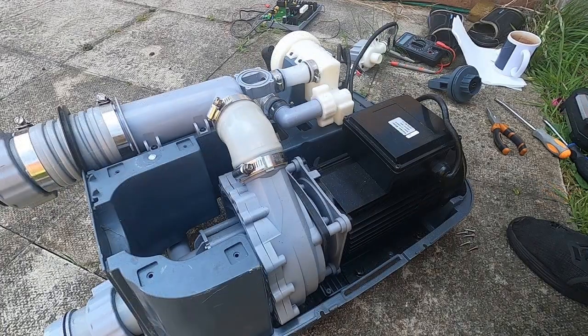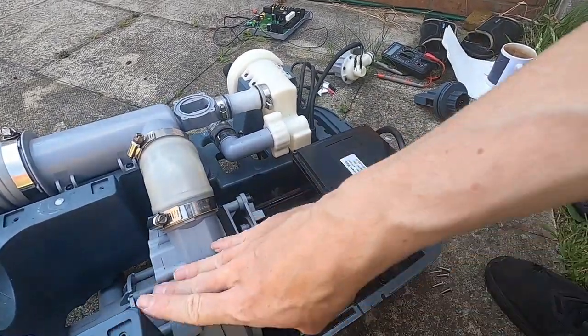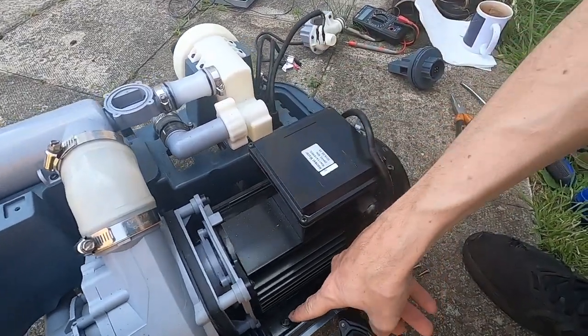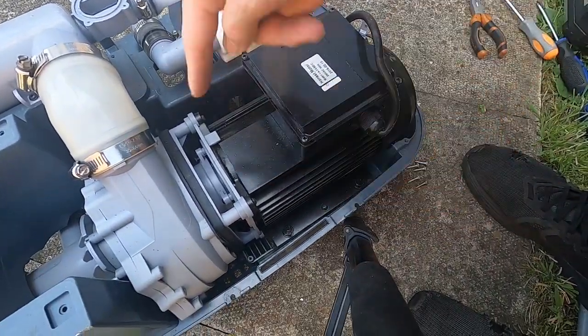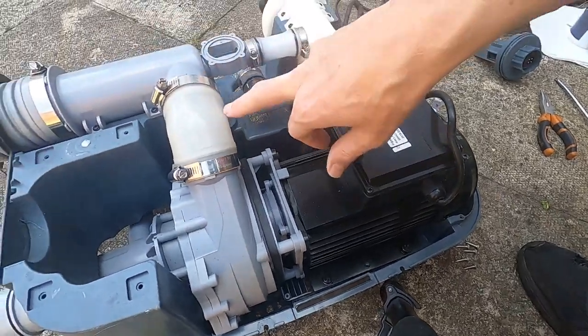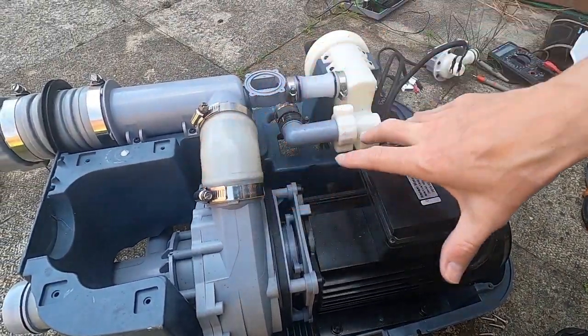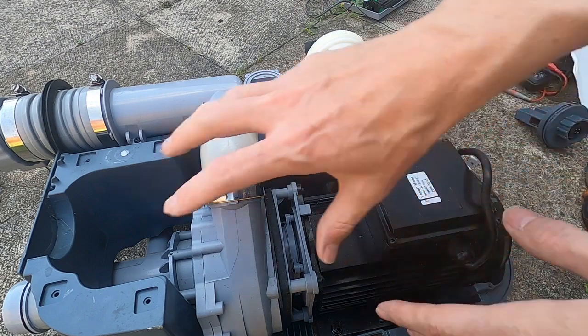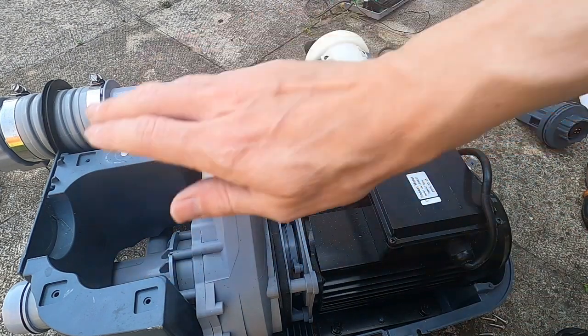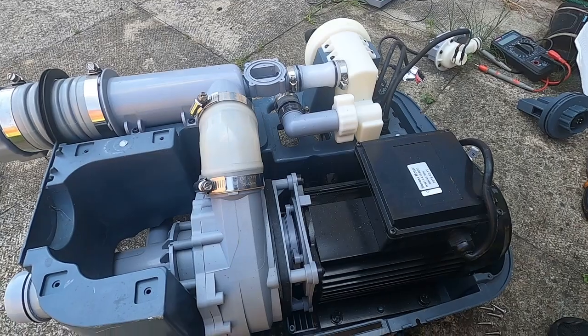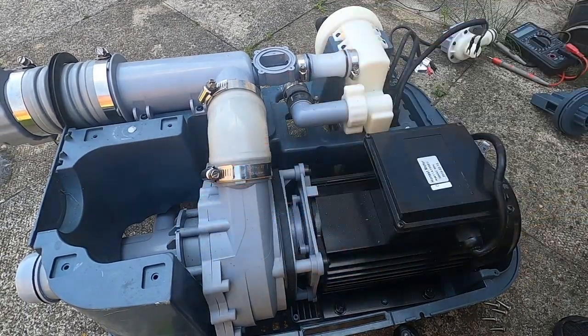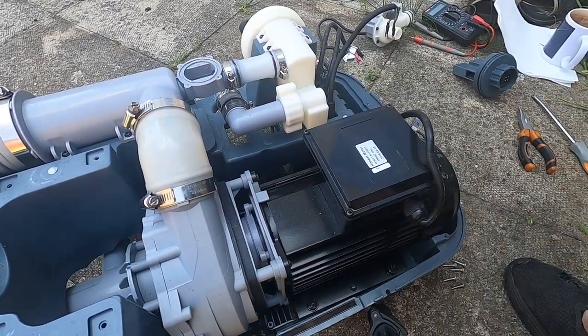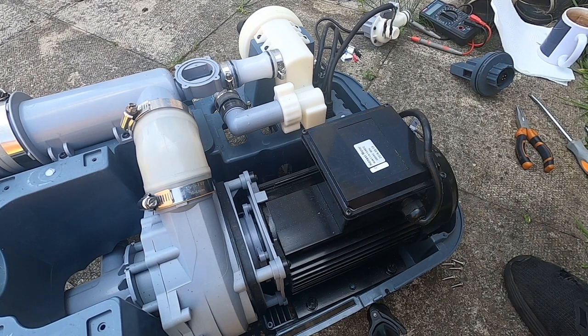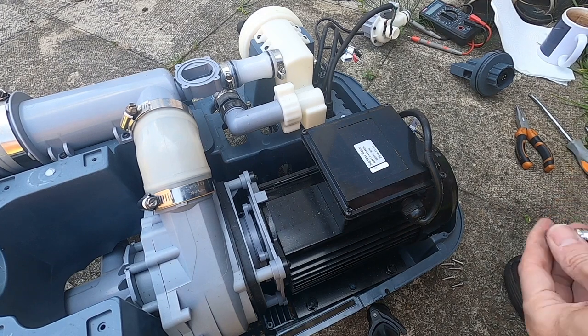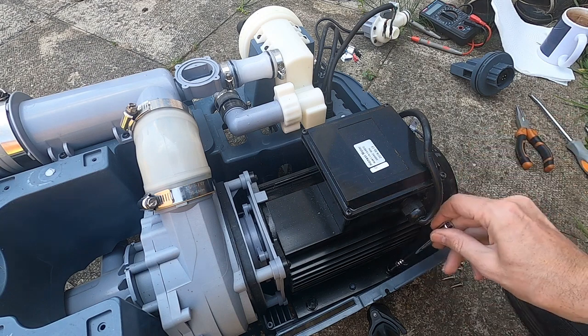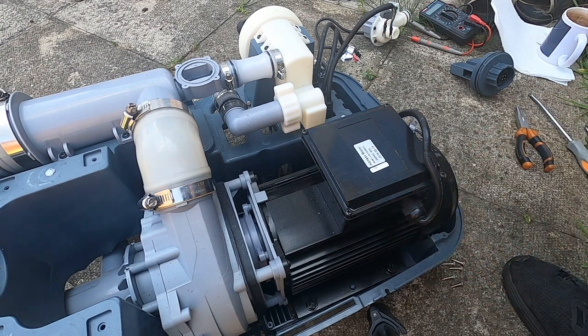Well, I've got to say, I've made a mistake there - the only way to get at that is actually to take the pump off. So I'm going to get a socket onto there, take the 4 bolts off, disconnect this pipe, and then with a bit of struggling we should be able to take this whole assembly out. At least then we can easily get at it and clean out the internal seals. I was trying to sneak my way around it, see if there was an easier way of doing it, but there isn't.